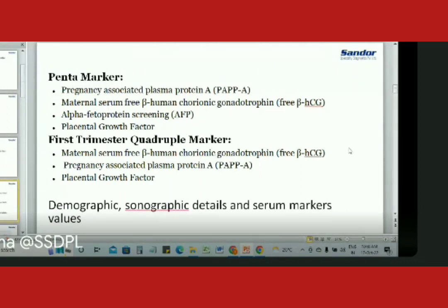In the market, we have Prisca as well as LifeCycle. LifeCycle is from PerkinElmer. Victor 2D or AutoDELFIA, these instruments are from PerkinElmer. It's a closed system. We use LifeCycle software for calculating the risk. Basically, the instrument is used to note down the readings, like the concentration of these particular proteins or hormones present in the serum sample.